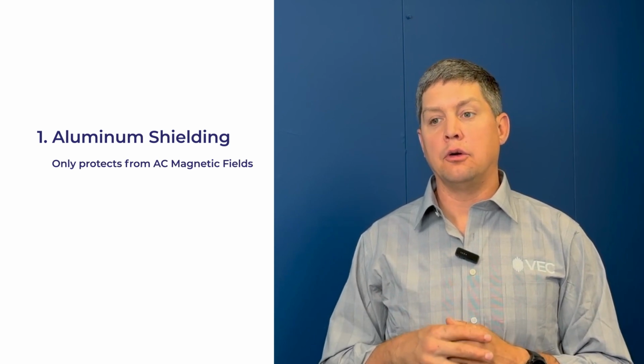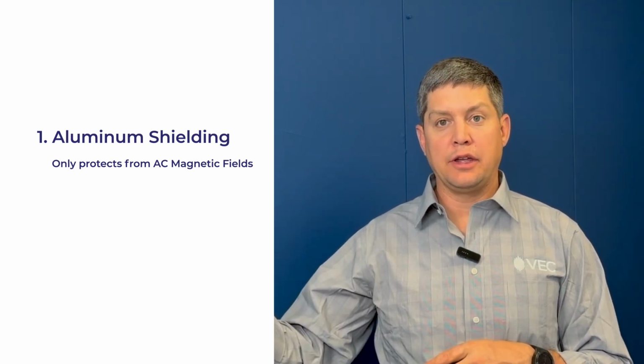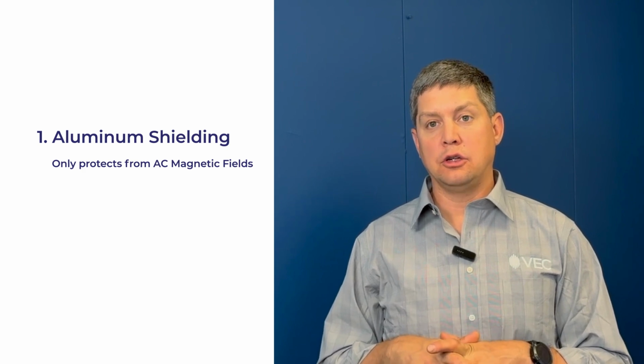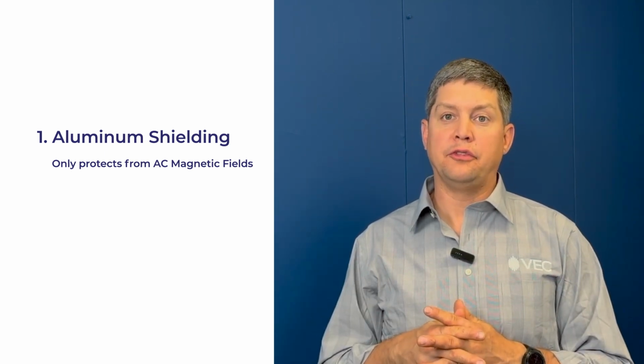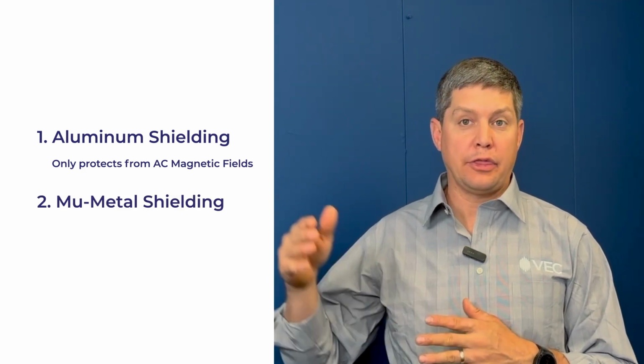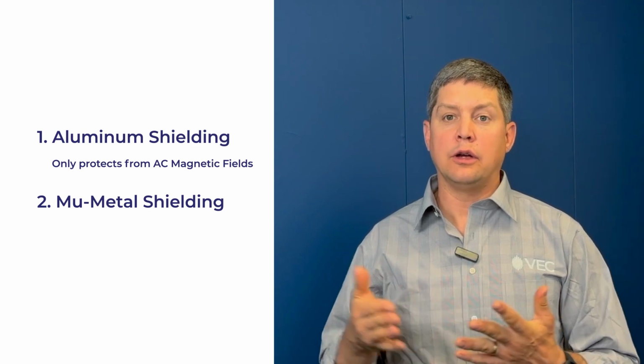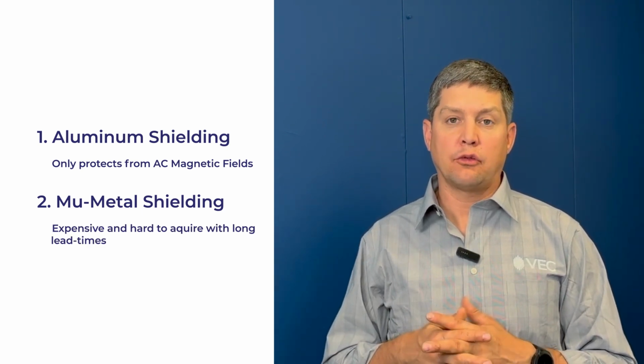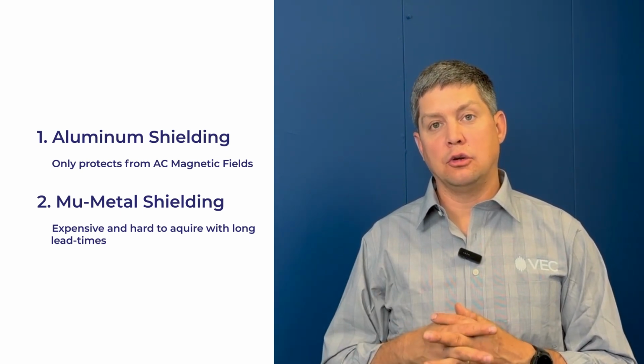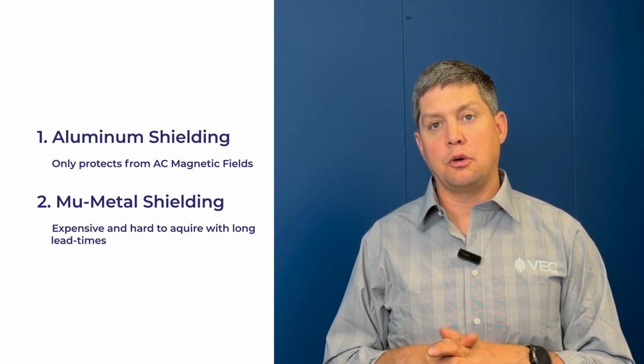One is, if you do eddy current shielding, aluminum shield your lab, you really only protect yourself against AC magnetic fields. So, the tight specifications for the microscopes, say 20 nanotesla peak to peak. Yes, you might shield the AC component of it with aluminum, but you're still going to need to mitigate the DC component from trains, elevators, or activity around the laboratory. Well, why don't we explore both DC and AC shielding? Why don't we use mu metal shielding? Well, that works and certainly is an option. However, it is very expensive, and the lead times for these materials are often years. And so, although it is an effective way to shield your laboratory, it's often timeline and cost prohibitive for many customers.